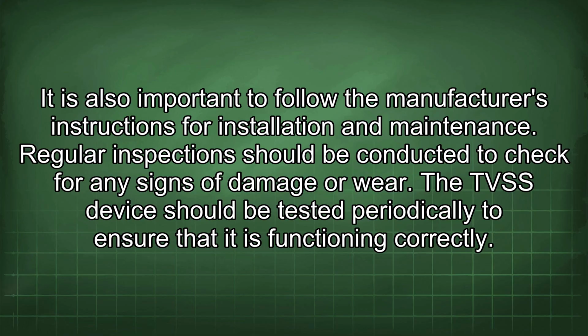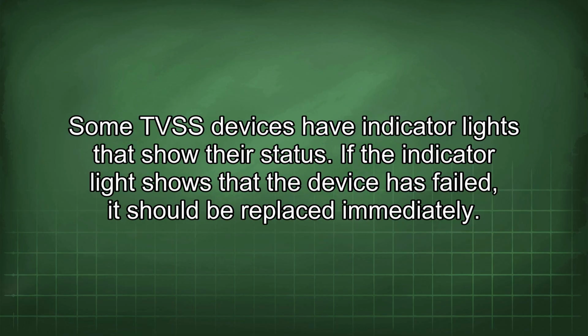Regular inspections should be conducted to check for any signs of damage or wear. The TVSS device should be tested periodically to ensure that it is functioning correctly. Some TVSS devices have indicator lights that show their status. If the indicator light shows that the device has failed, it should be replaced immediately.